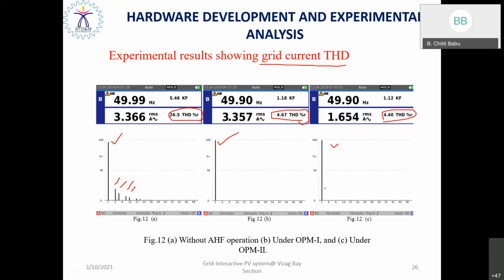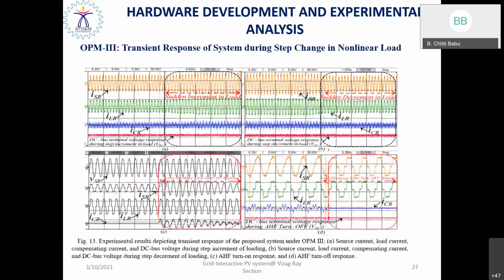You can see it injects only the fundamental current component of 50 Hz. And moreover, it satisfies the IEEE draft 519/2014 standard. That is a very important standard in the control technique. It has to satisfy. This is the transient response during step change in non-linear load.